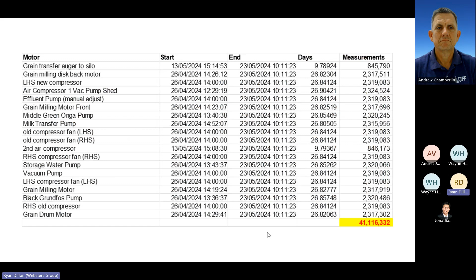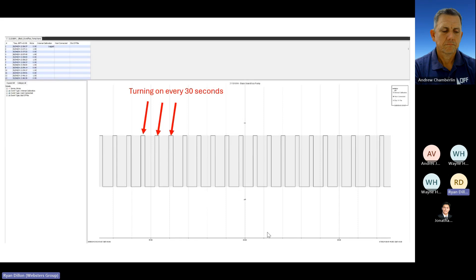And we wouldn't have seen that in the 30-minute interval data from the main meter, or if we hadn't focused on the devil being in the detail. So this pump's turning on and off every 30 seconds. And in this instance, the pump actually is for a storage tank, and the storage tank's filled by a bore pump. So in the annual energy balance, you would see a segment that shows bore use, but on a daily profile, here in green, we actually see this bore pump.